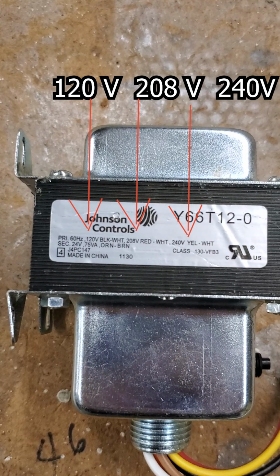And depending on what kind of circuit you're going to hook up to, if we look at the back at the 120, the colored wires are right next to it. So 120V, BLK-WHT. BLK stands for black, WHT stands for white. So you would hook up the black and the white wire to a 120 volt circuit. As you would for the 208, you would put it to the red and the white wire. And 240 would be yellow and white. But in most cases, you'll see that they just run 120 volts to the panel. So in most situations you would do black and white with this specific transformer.